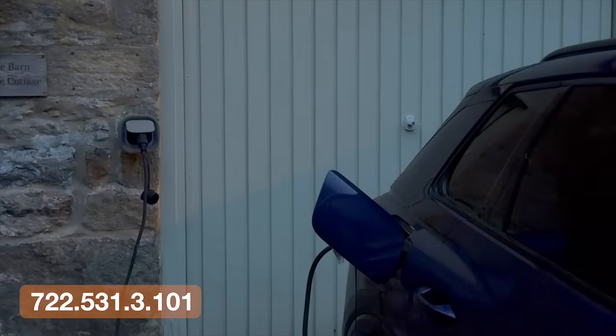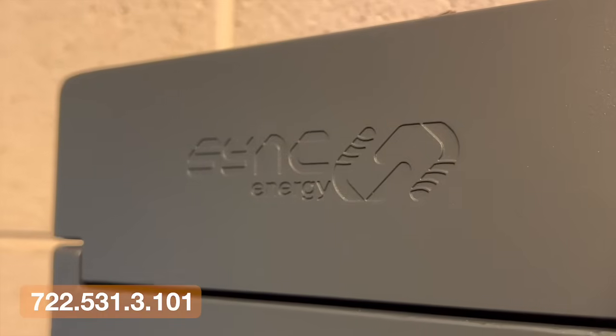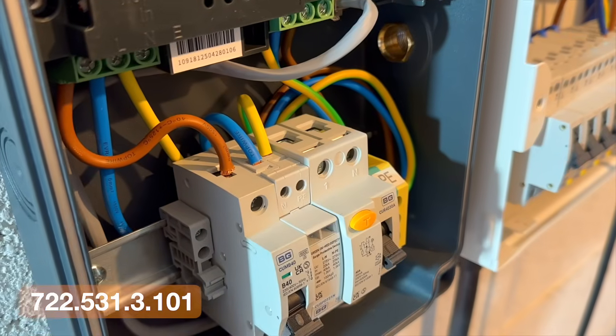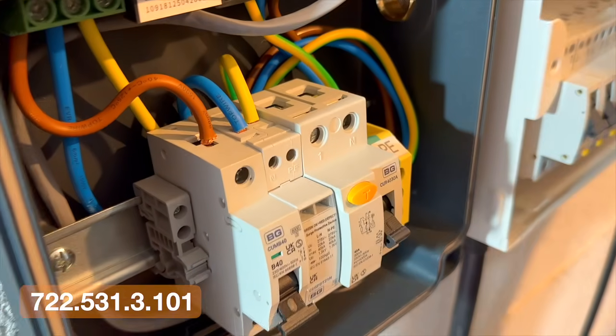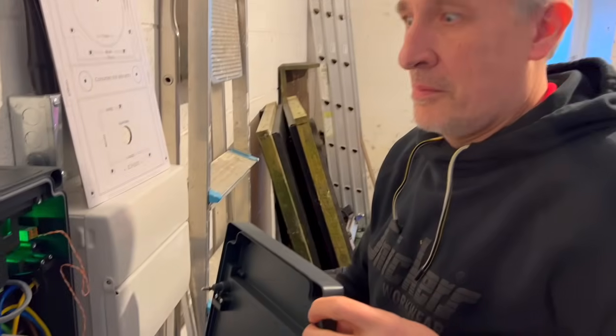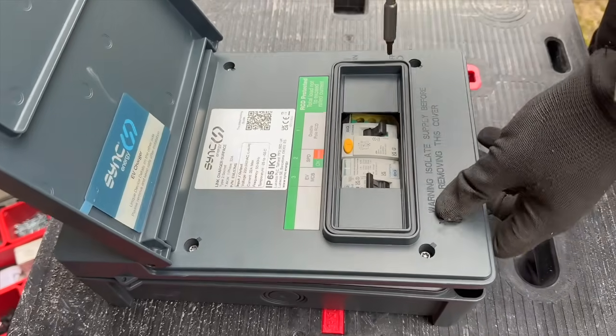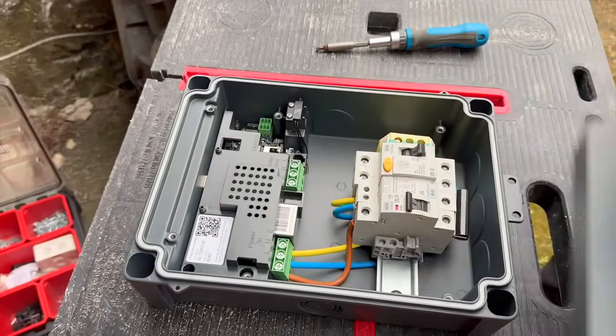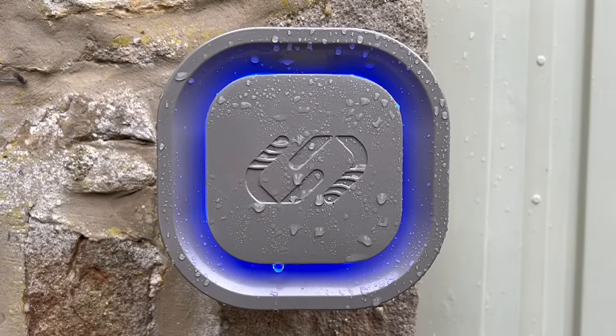So in practice, that can simplify your installation. It can change board layout and it reduces the need for additional protective devices upstream. But it does rely on you understanding exactly what the charger is providing and confirming that it meets the required standard. So you cannot just assume all chargers are the same. There is also clarification around AFDDs. AFDDs are not required for EV charging equipment that conforms to BS EN 61851. So this removes some of the uncertainty that was starting to build around whether this should be included.